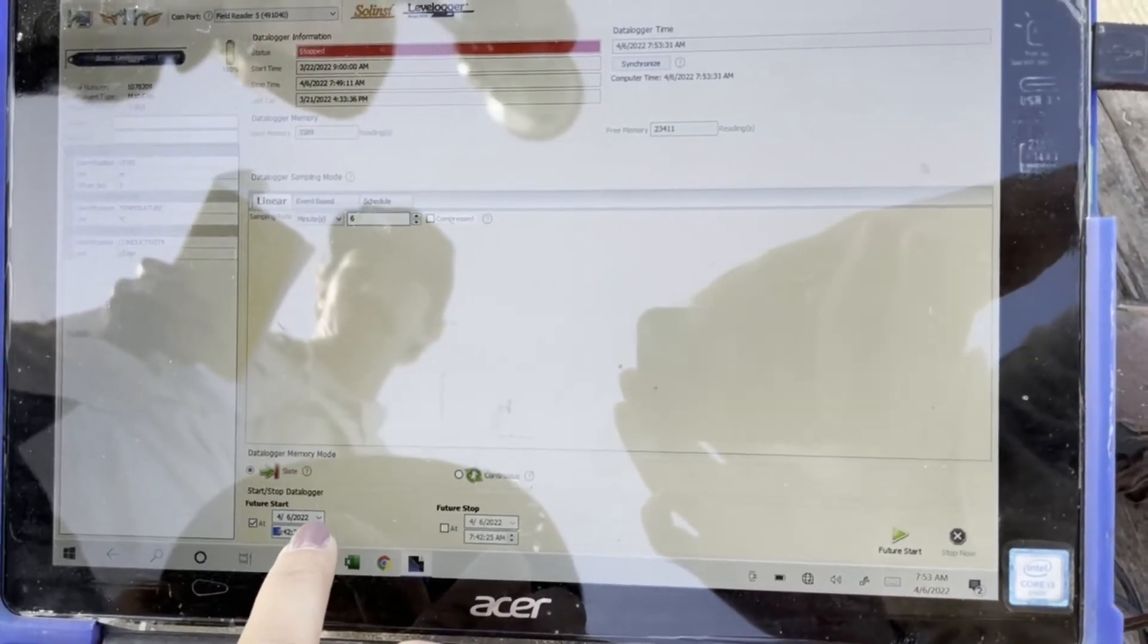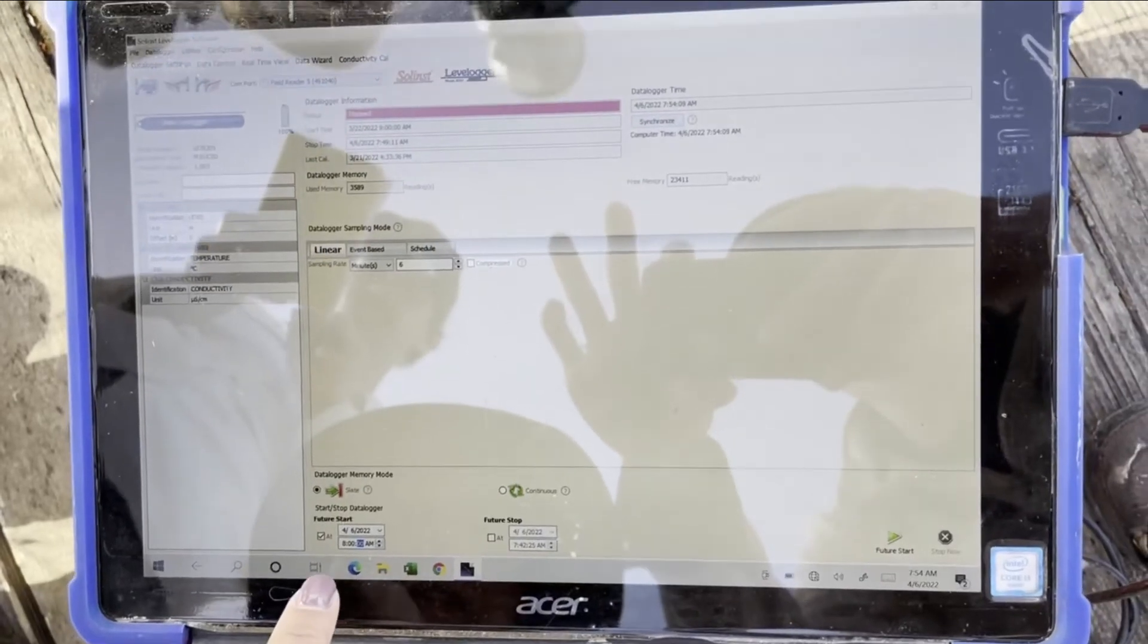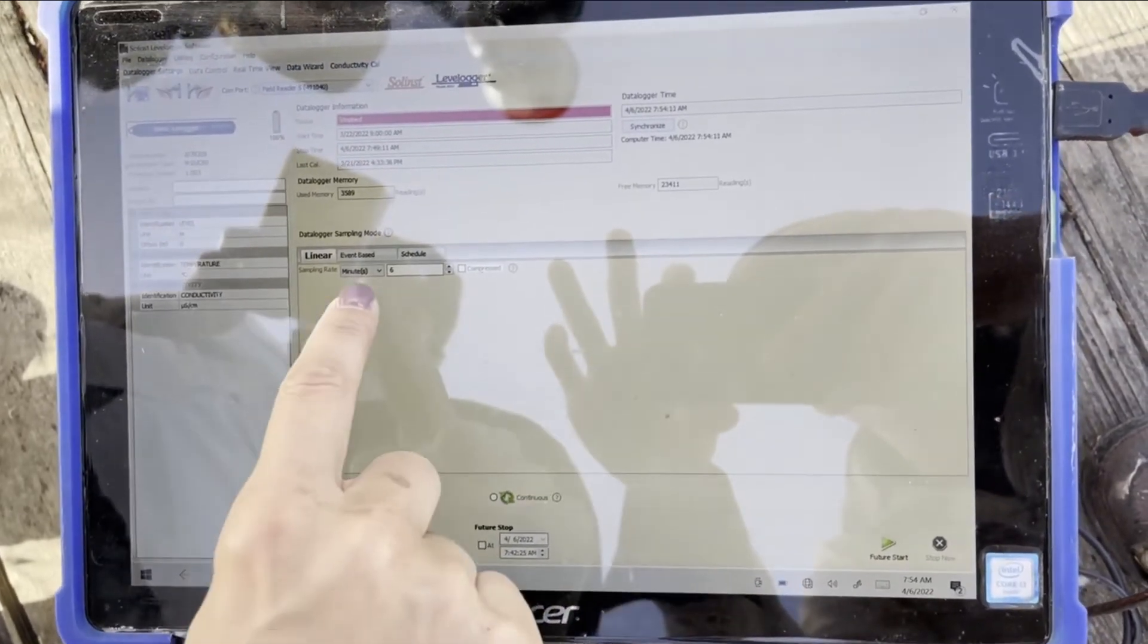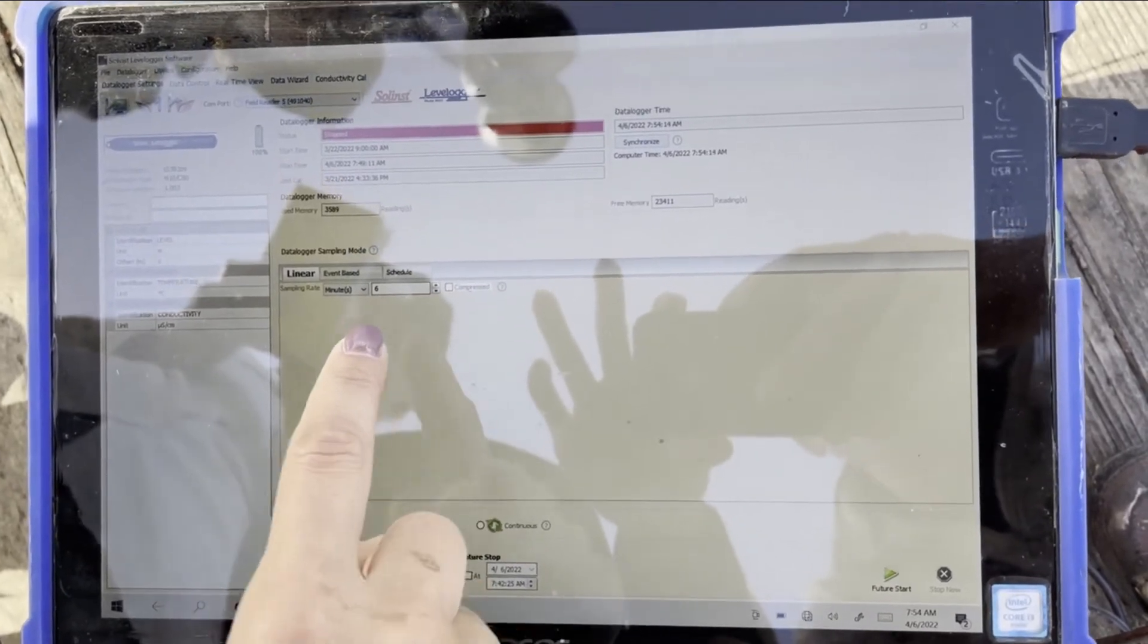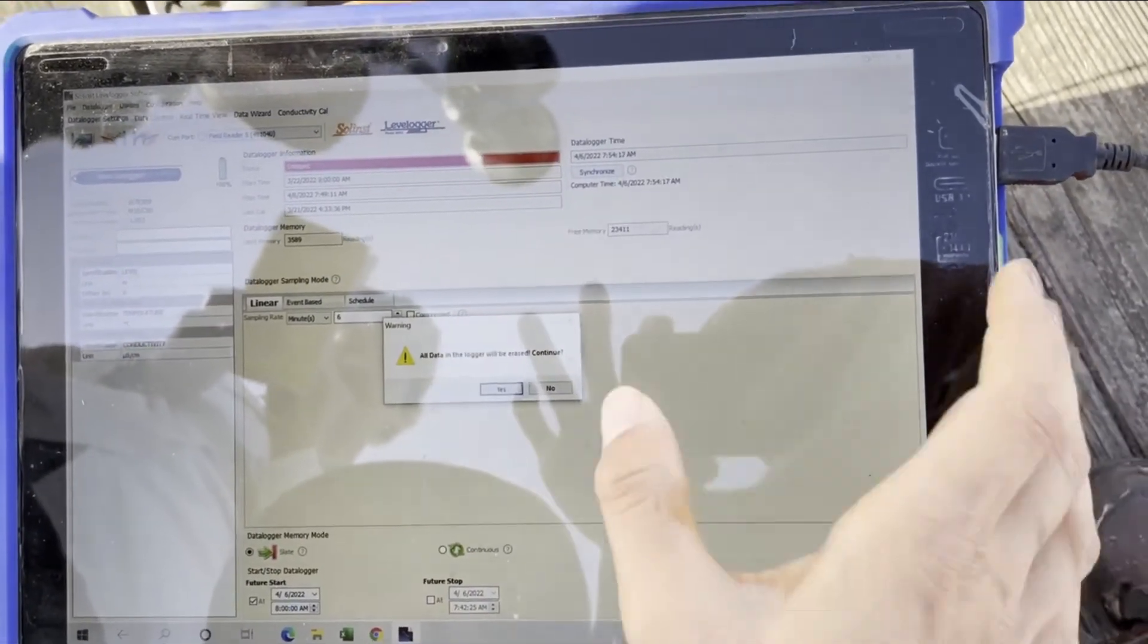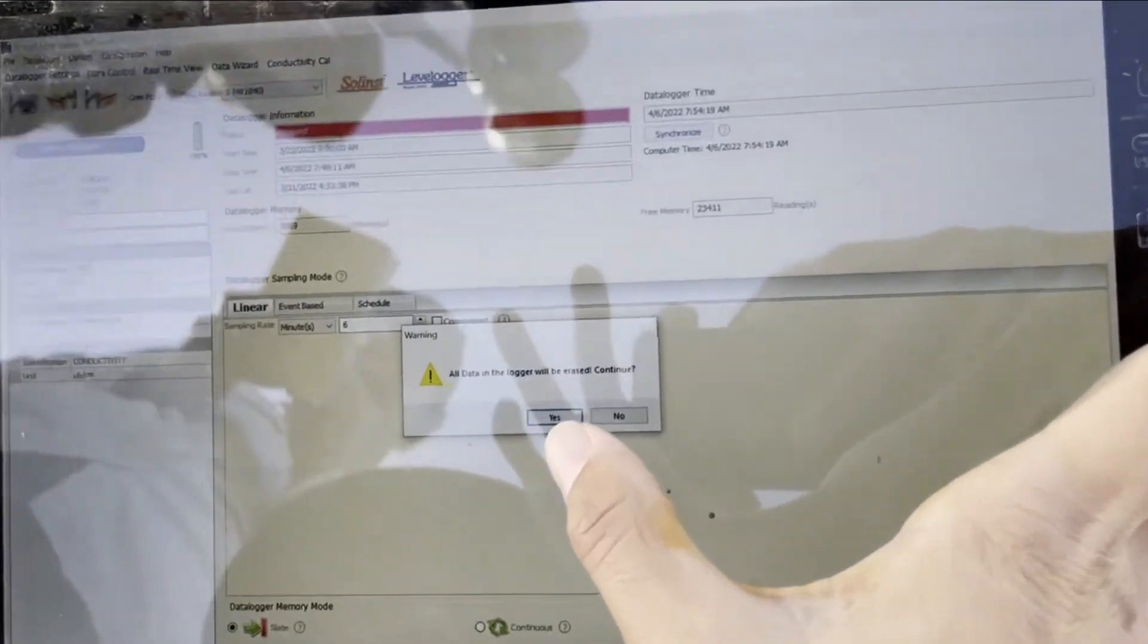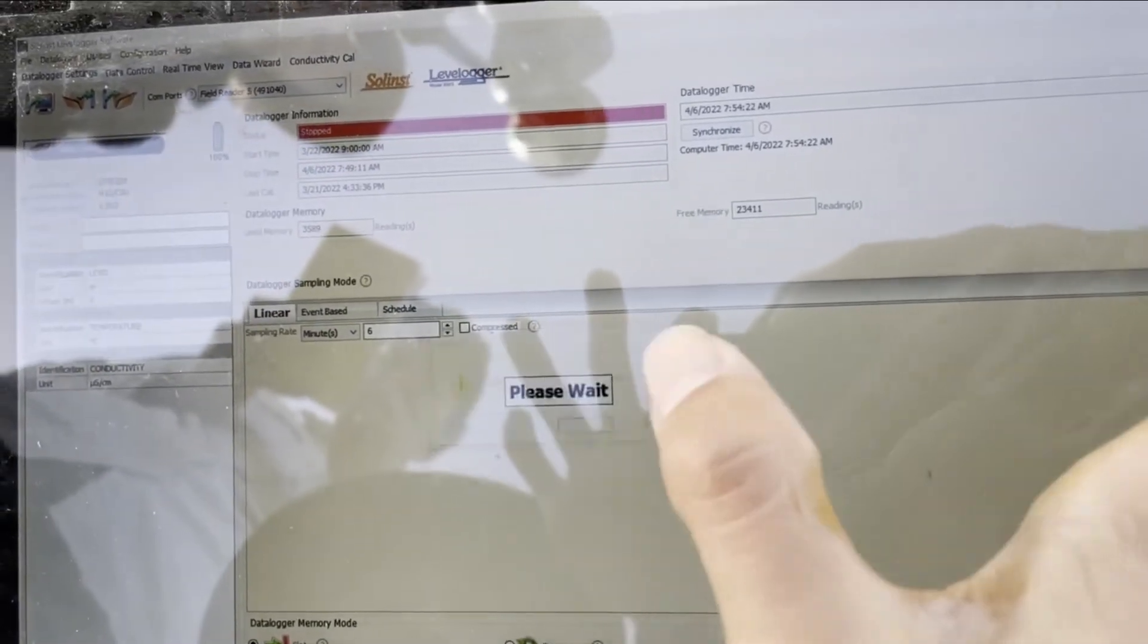Let me pause that. For what time I'd like to start it, which is at the top of the hour, we're doing six minute intervals and I'm going to hit future start. It'll give you some warnings. All the data in the logger will be erased. That's fine because we just saved it all.